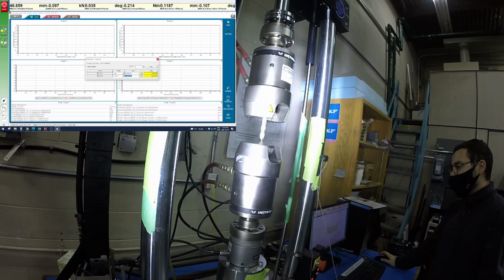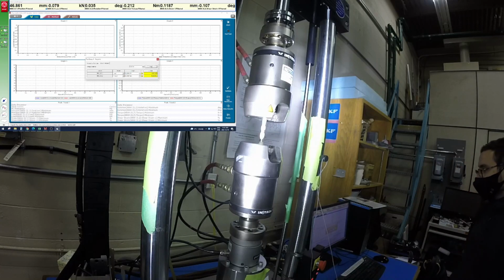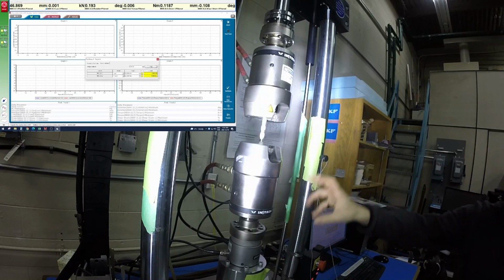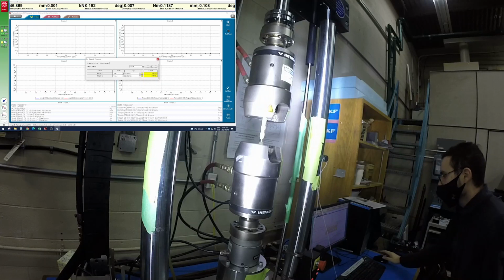This Instron WaveMatrix software is quite unintuitive compared to Windows, in the sense that you have to click enter to log one of these changes in any of these fields that you're selecting. So I'll click start, and you'll see both of these values start to decay to 0 over the course of 5 seconds. And now we know that the sample's under no real residual load, which is nice, because then we can apply the extensometer and we can balance all of the directions of that extensometer to read 0 effectively, because we know that the sample's under no load based on the load and torque coming from the transducer.